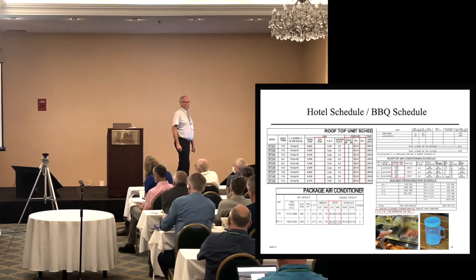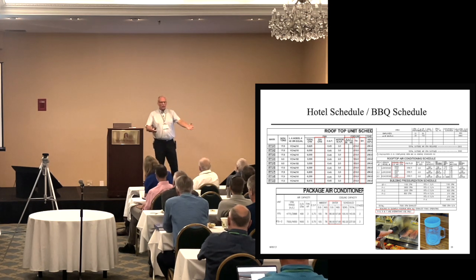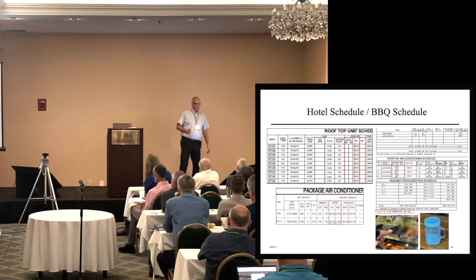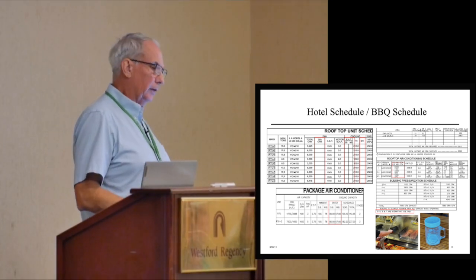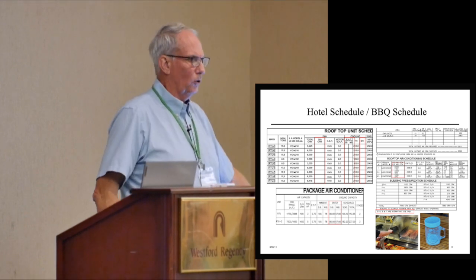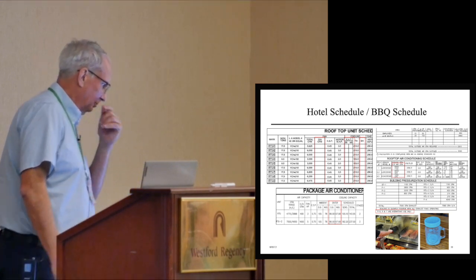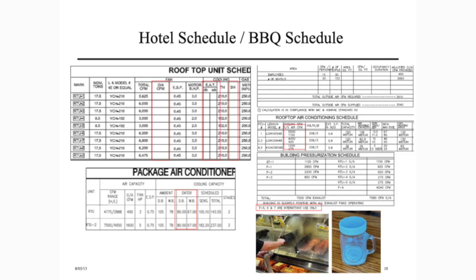And one of the big claims they were making in the lawsuit was that our client had installed the wrong air conditioners. Even though when the submittal went in and got approved, they corrected the typo, they went back to the original drawings and said, you did it wrong, therefore you're being sued. Okay? So I'm just going to drop down to the next equipment schedule below that. There's the 80/67 entering conditions. Okay? That's a red flag.